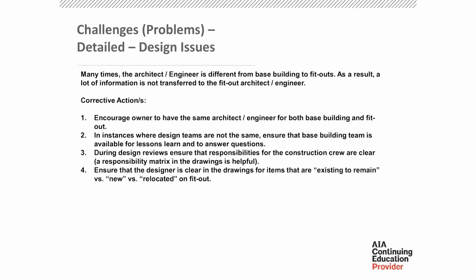One particular project we had pulled in temporary chillers and boilers and placed them inside the garage, because it was a 750,000 square foot building and they were only going to operate about 25,000 square feet on day one. Many times the architect and the engineer are different for the base building and the fit outs. As a result, a lot of the information is not transferred to the fit out architect or engineer. So corrective actions: encourage the owner to have the same architect and engineer for both base building and fit out. In instances where the design teams are not the same, ensure that the base building team is available for lessons learned and to answer questions.